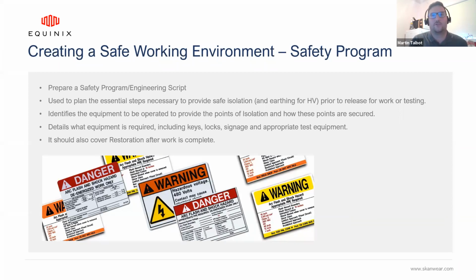Once we've got the RAMs and we've agreed a day when we're going to do the job, we want to prepare a safety program or some kind of engineering script. And it's going to tell us how we're going to safely isolate the switchboards. I always recommend having some kind of safety program or engineering script for doing something complicated. And by this, I mean a high energy switchboard with more than one source of supply that you could get wrong. So you could, at worst case, hurt someone or drop supplies to a customer. So it identifies all the equipment that we're going to operate, the points of isolation, how these are secured, what equipment we need to do this, keys, locks, signage, test equipment if required, and then we're also going to cover the restoration afterwards.